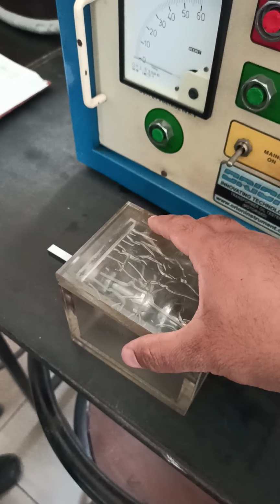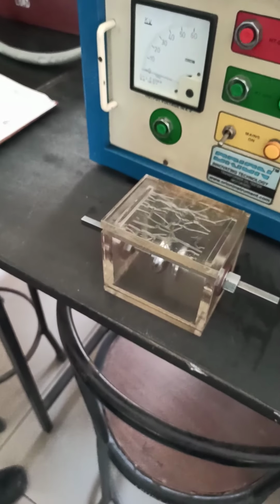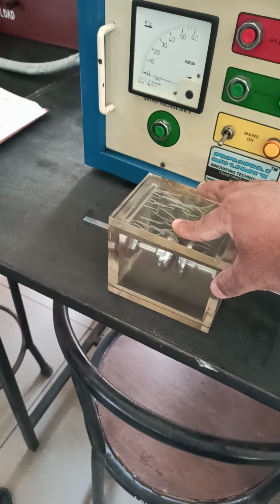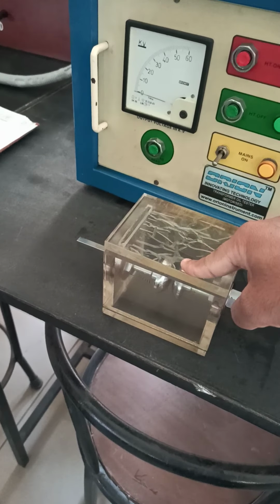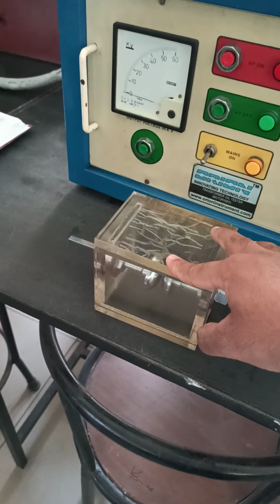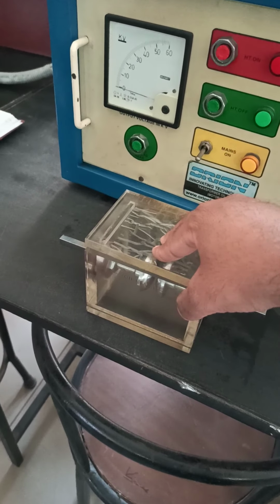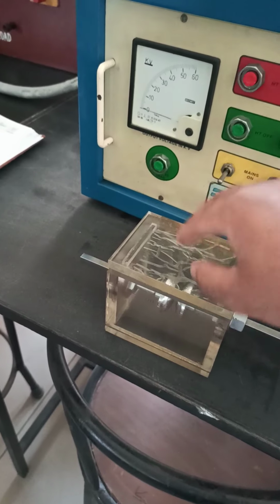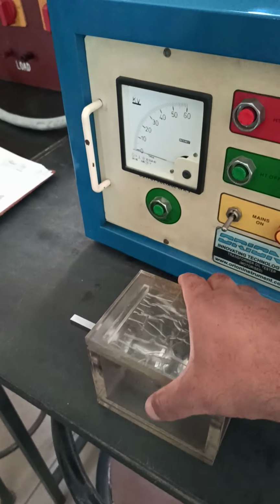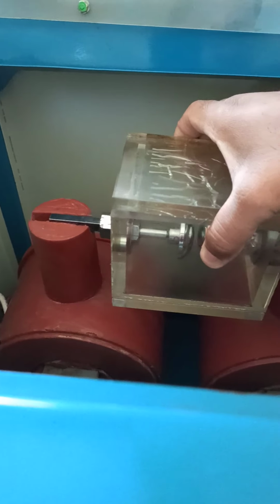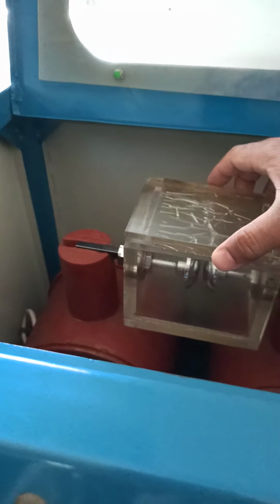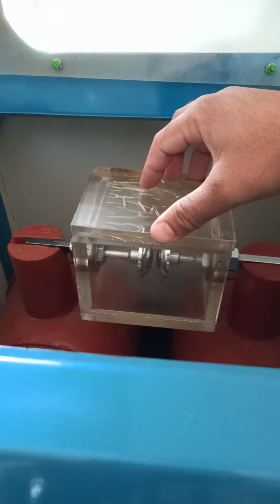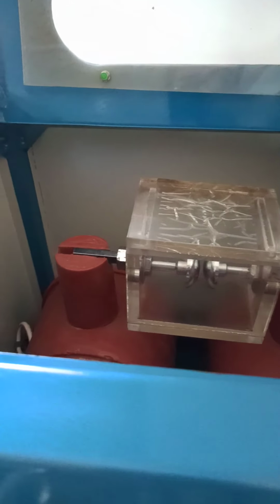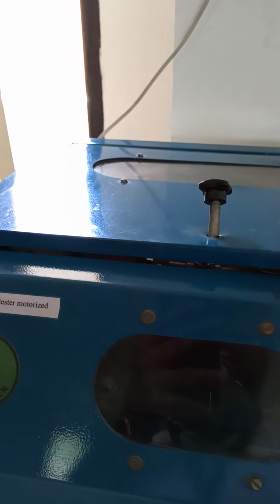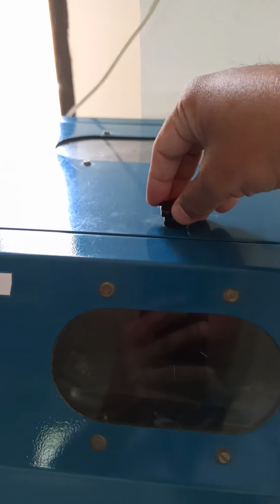Whenever you are performing the practical for transformer oil, you need to pour the oil in this box. Okay, after making the settings, first you will empty the oil, then you will make the gap, and then again you will pour the oil in this, and then you will place it over here where this arrangement is given for placing this box. Okay, it should be placed over here. Now I will close this lid. Make sure that this lid is properly closed.